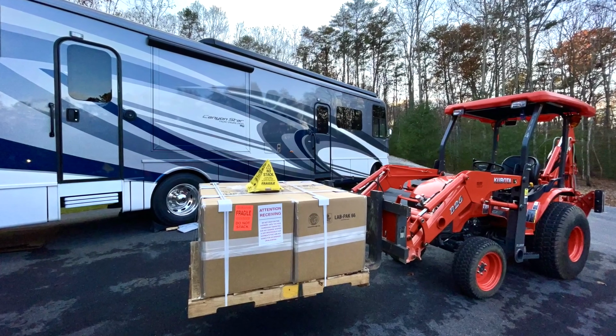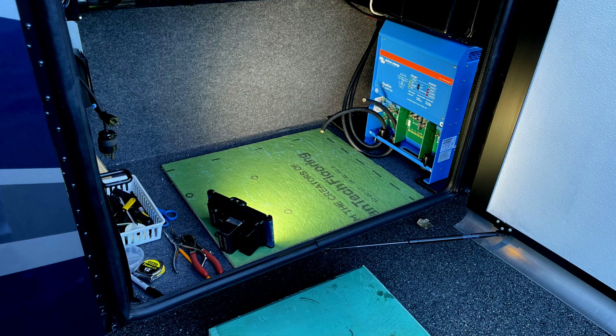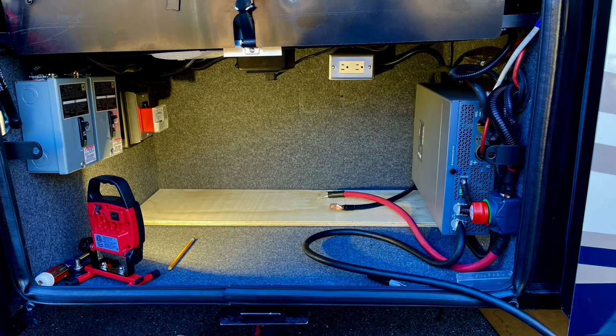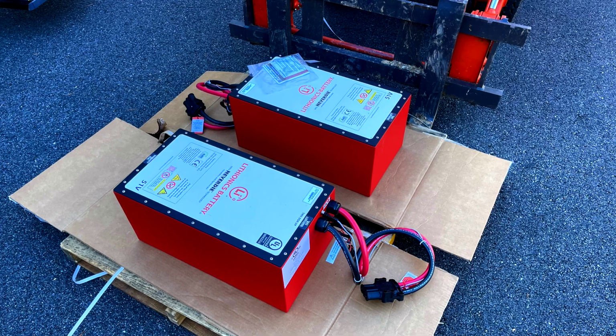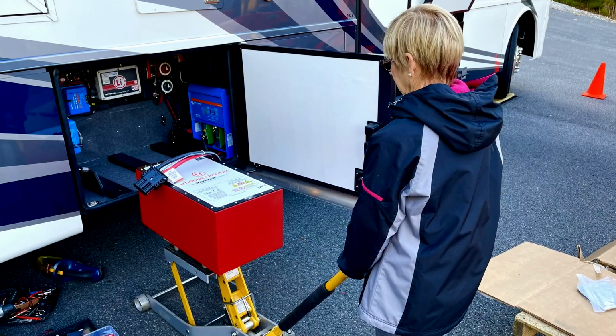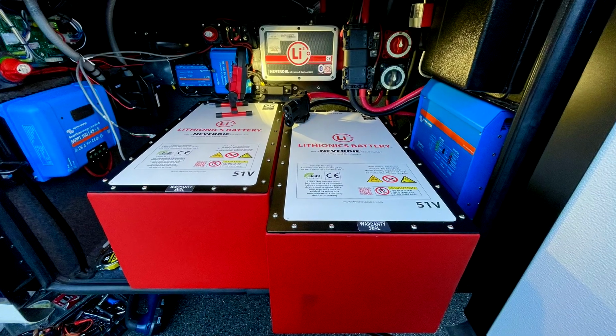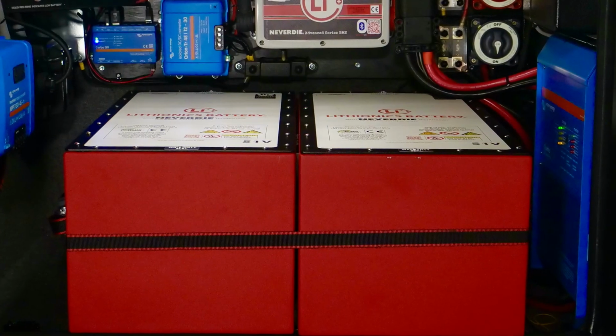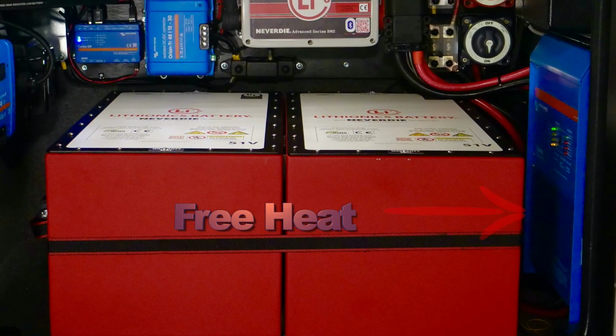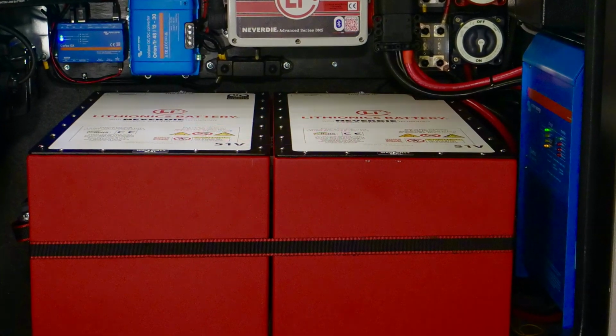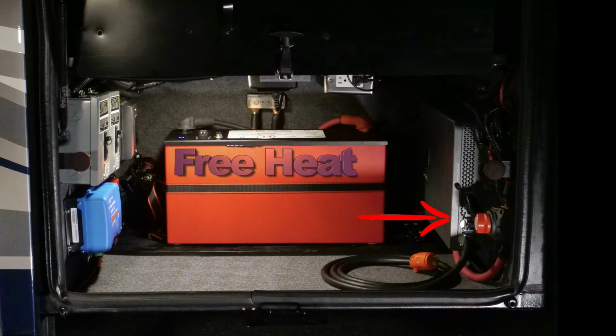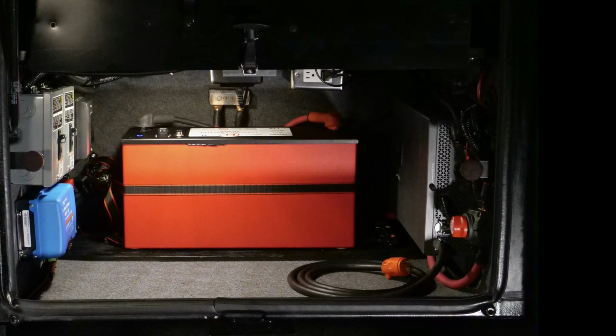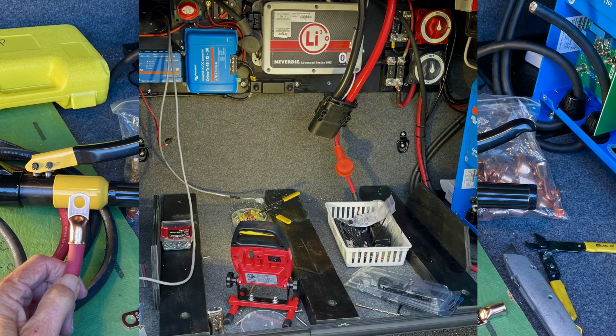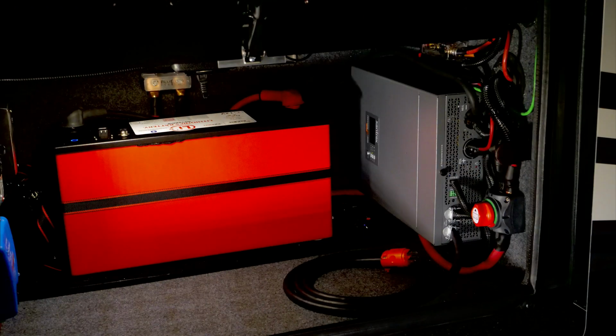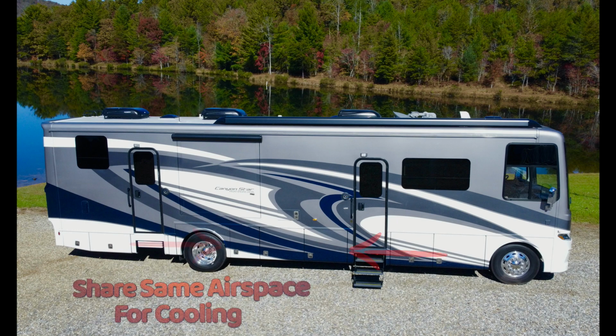Since the compartment floors are generally bowed, I manufactured non-metallic battery supports which span the battery's weight equally to the compartment's walls. Side bracing was also used to prevent unwanted battery movement and further secured with a winch strap. To minimize use of the Lithionics internal battery heaters, I deliberately positioned the batteries adjacent to the inverter so the batteries could benefit from free heat generated from the inverter itself during winter. This position also allows the batteries to be cabled just inches from the inverter for near zero losses. For summer use, all 6 compartments now share the same airspace for ample summer cooling.